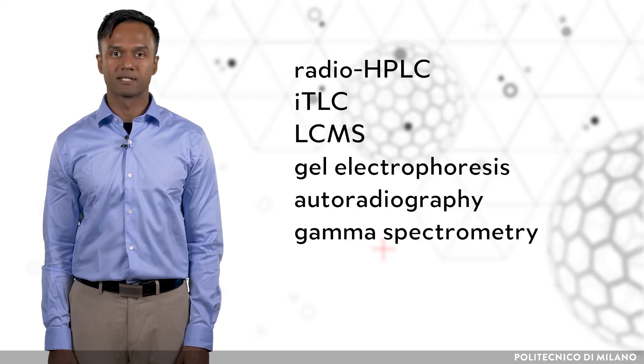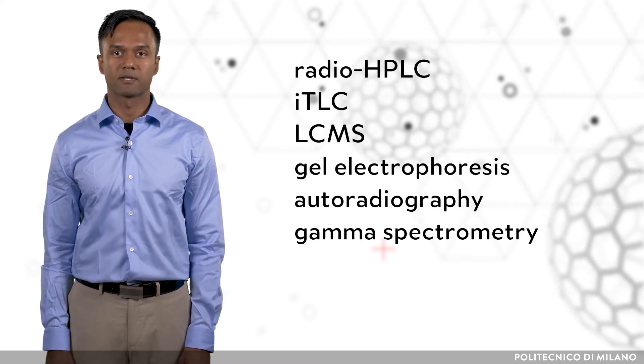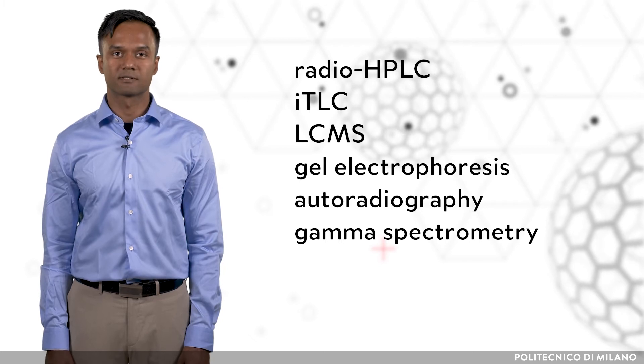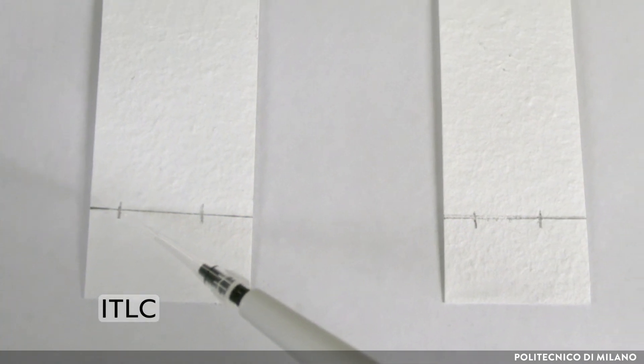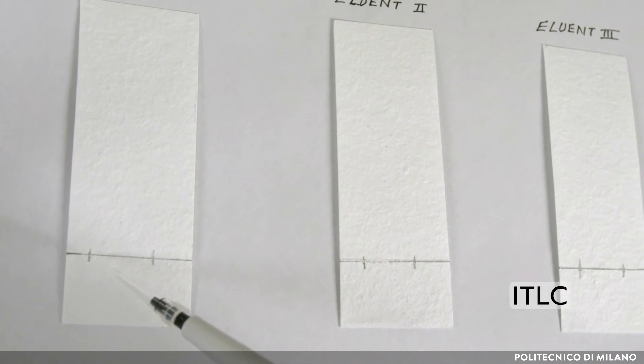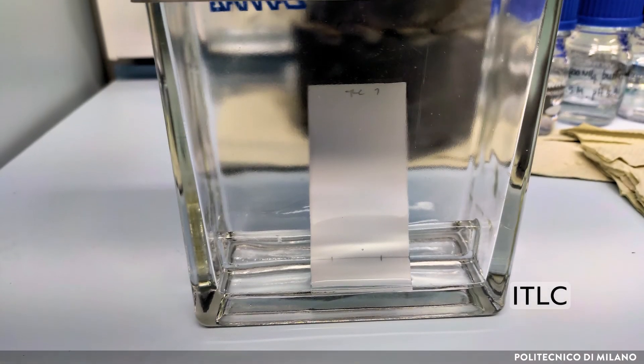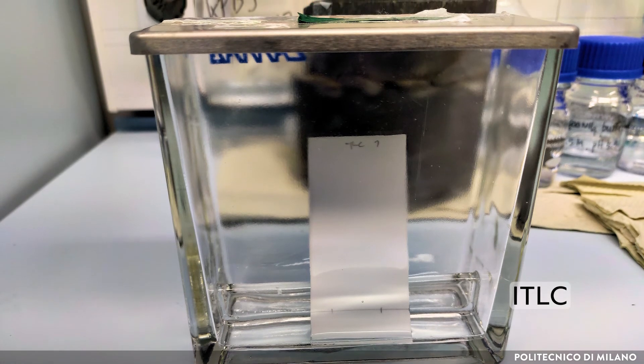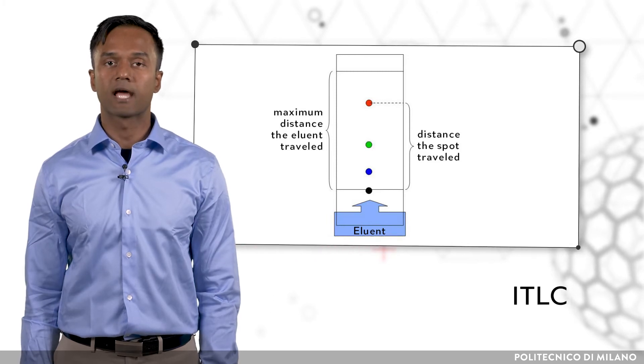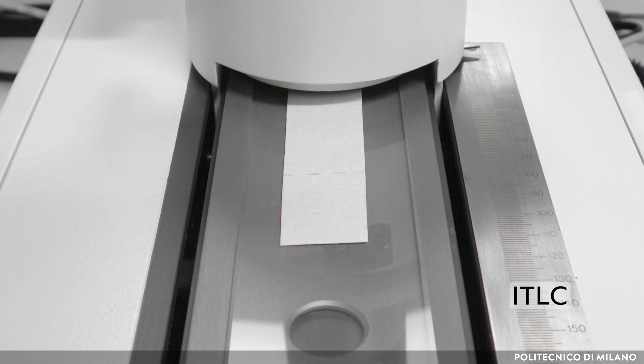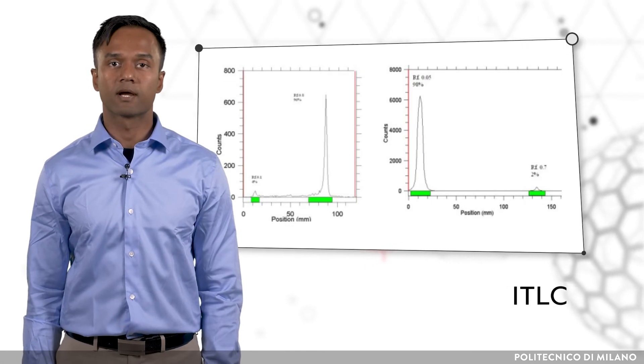Several techniques are used for quality control, including RadioHPLC, instant thin layer chromatography (ITLC), liquid chromatography mass spectroscopy (LCMS), gel electrophoresis, autoradiography, and gamma spectrometry. In ITLC, thin strips of stationary phase are spotted with analyte and mobile phase travels by capillary action, leading to separation of individual components due to differences in polarity. The ITLC scanner uses a gas-filled proportional counter to scan the whole TLC plate at one time, showing the number of radiolabeled species and whether there are any free radioisotopes in the sample.